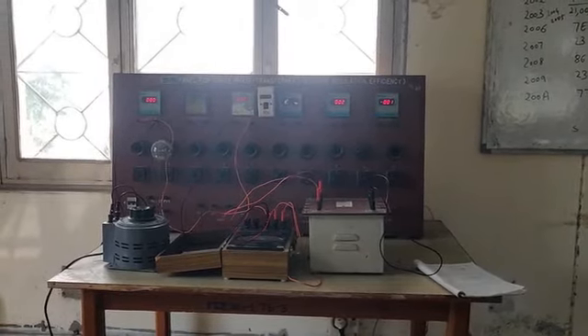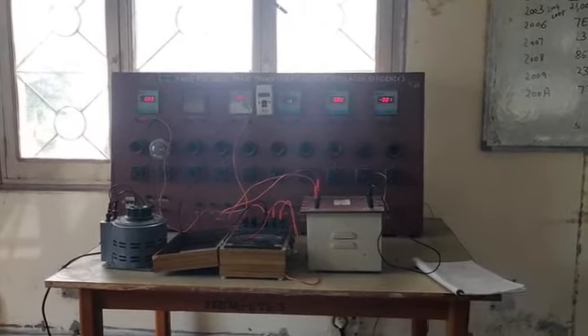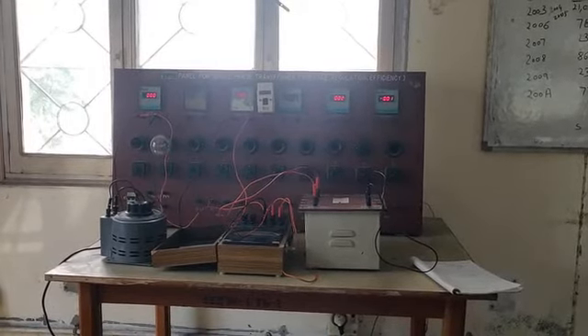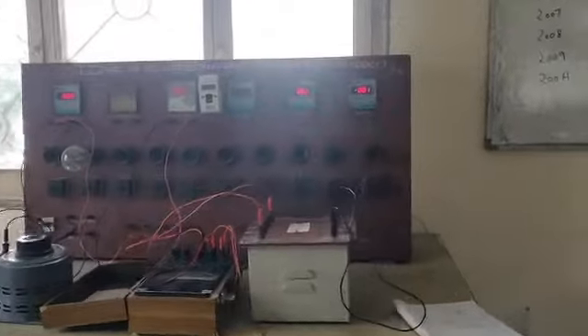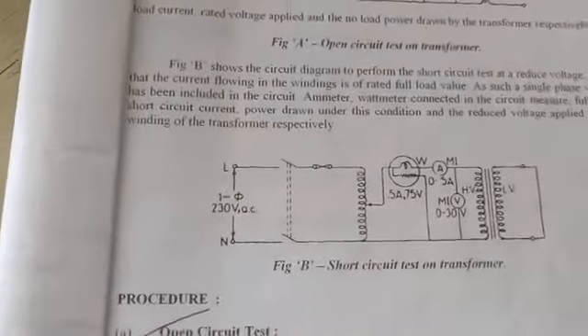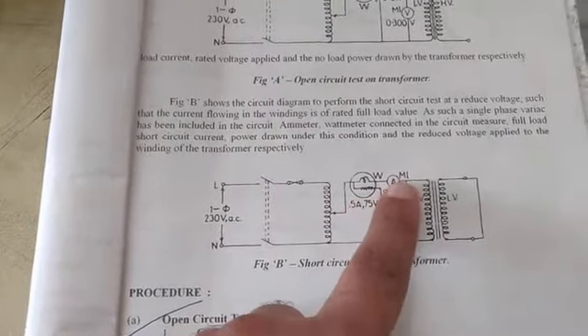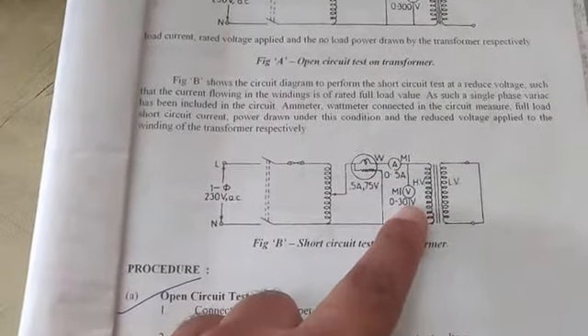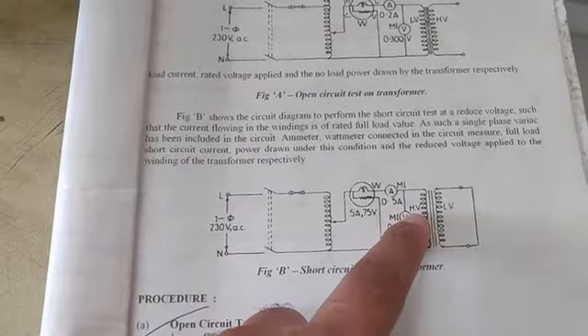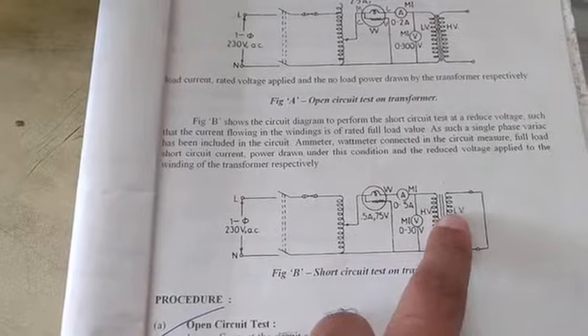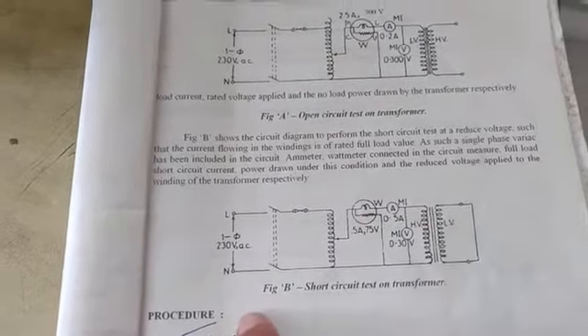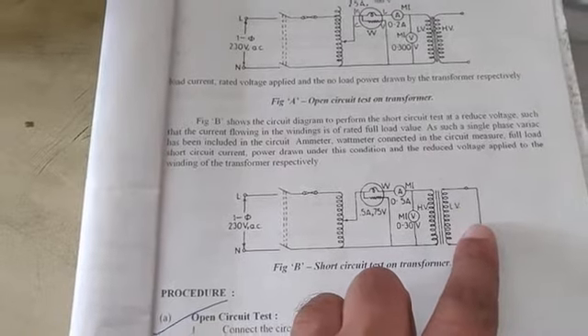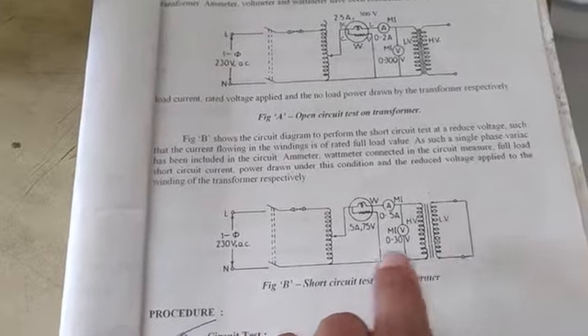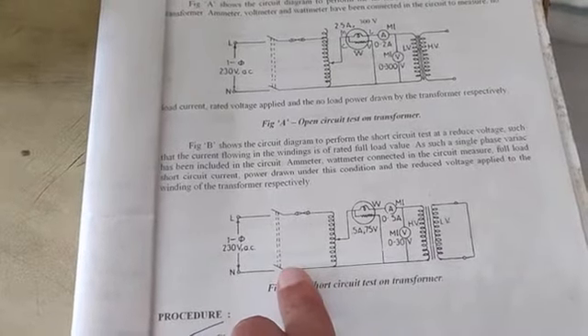So before I proceed with the operation of experiment, let us discuss the circuit diagram used to perform the experiment. In the circuit diagram, one tap changing transformer is used, one wattmeter, one ammeter, and one voltmeter. HV is called high voltage winding of transformer and LV called low voltage winding of transformer. In figure B, the low voltage winding, that is secondary winding of a transformer, is short circuit. So all the assembly is connected with the primary winding.